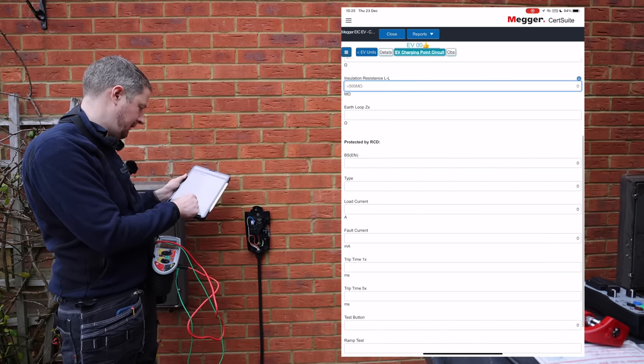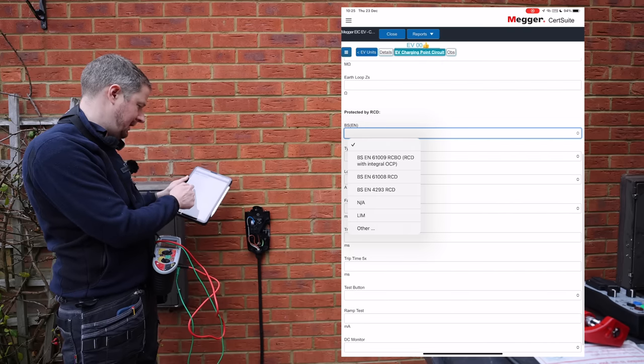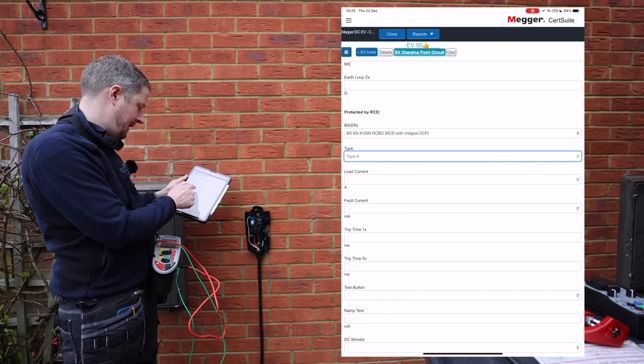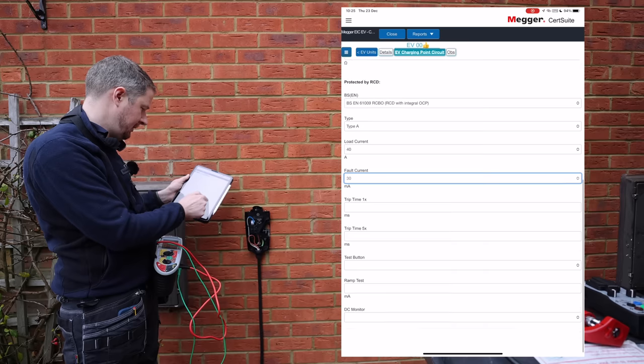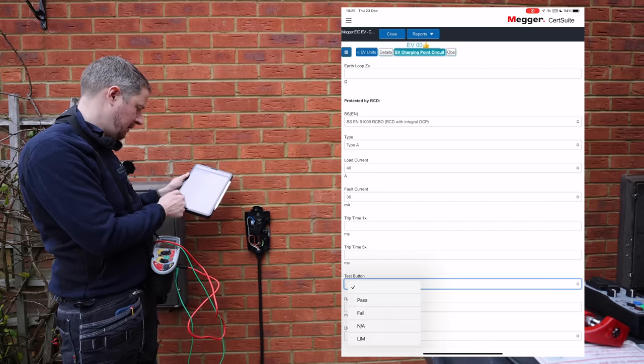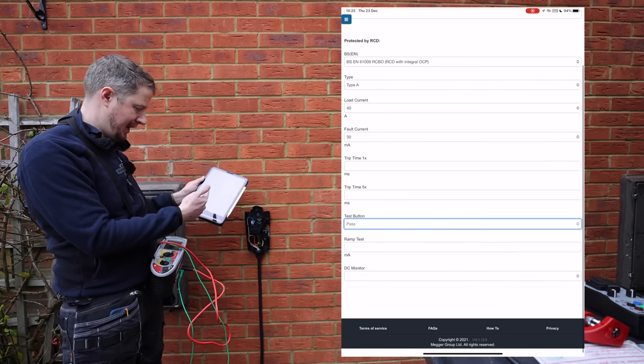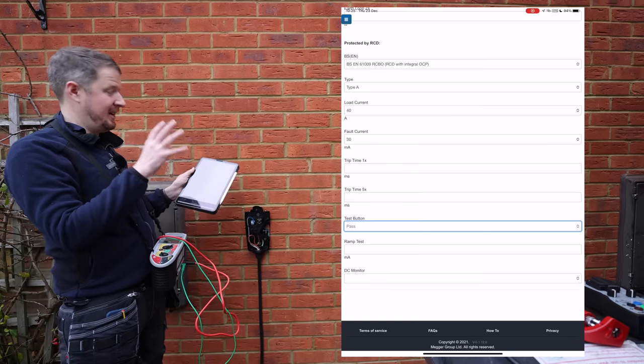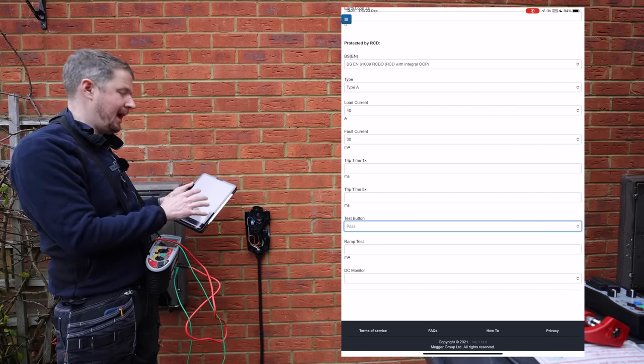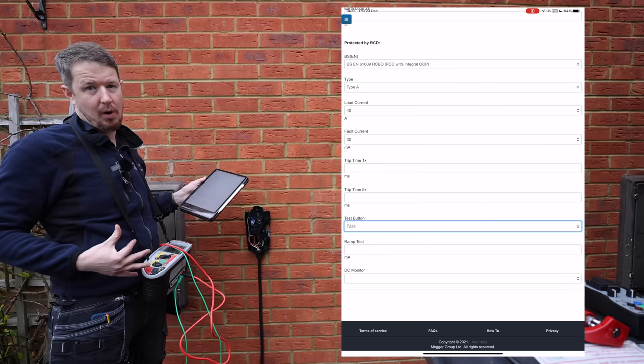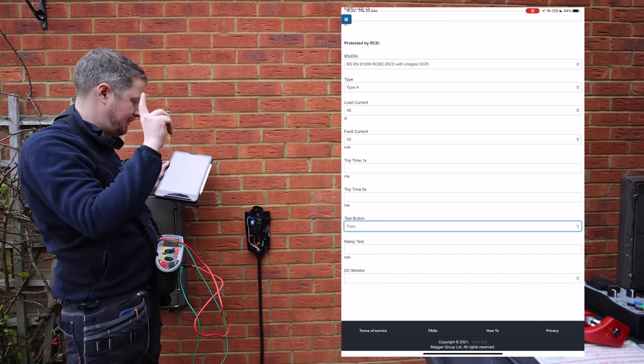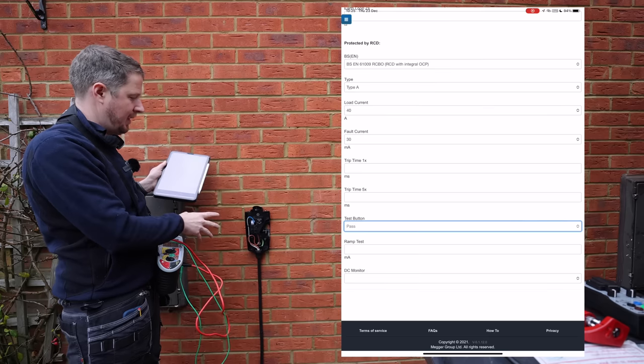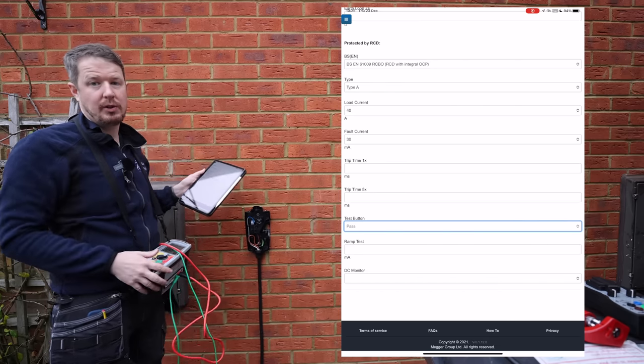Insulation resistance, we've already done, that's fine, that's off the scale. Earth loop impedance, we'll do in a minute once we liven it up. And then we've got our RCD test reading, so it's got an RCBO type A, 40 amp, 30 milliamp, and we do our trip times for RCD there as well. Pass for the thing. We can even do our ramp test, our DC monitor test, everything that you need for an EV testing-wise is in here. And it creates a beautiful one-page certificate with all the readings on, which looks really nice. So I'll jump back at the board, liven that up, we'll do our Zs here, then we'll put the cover on, we'll do our functional tests.